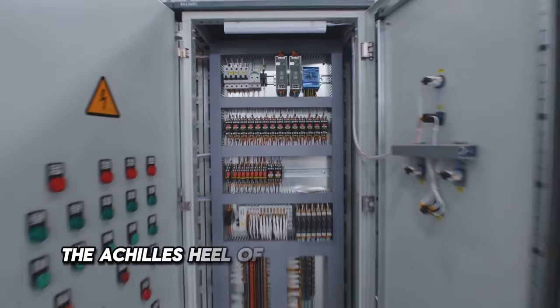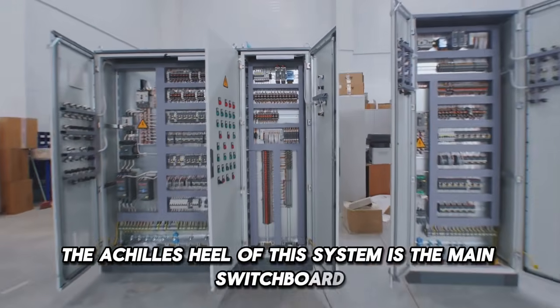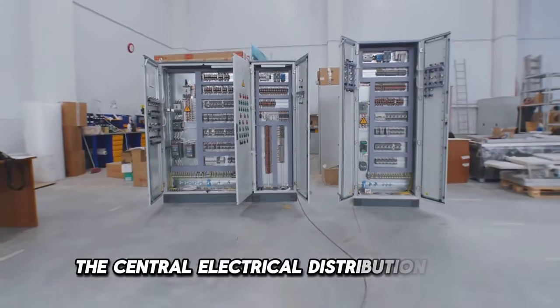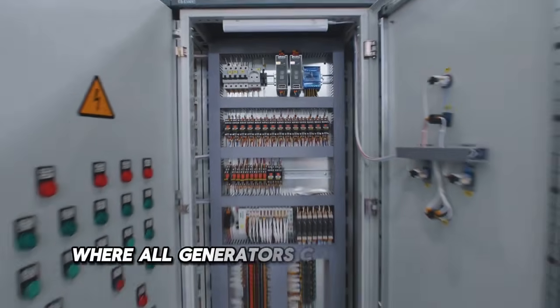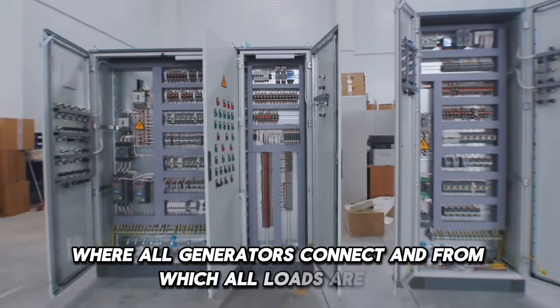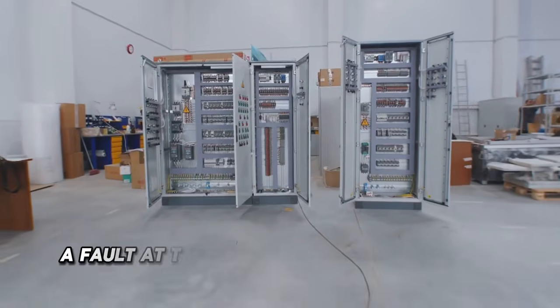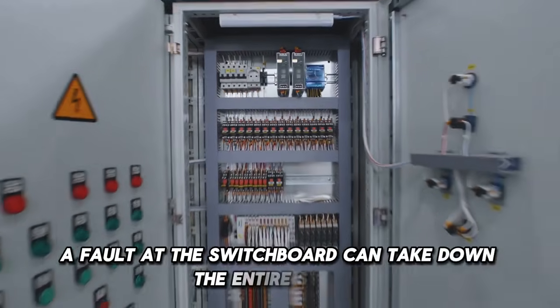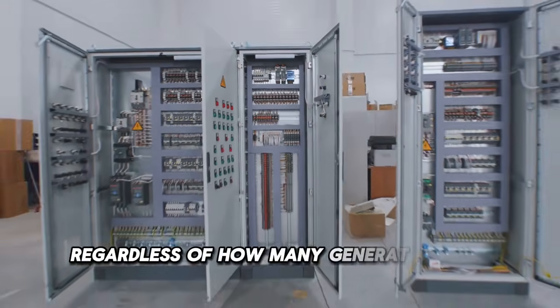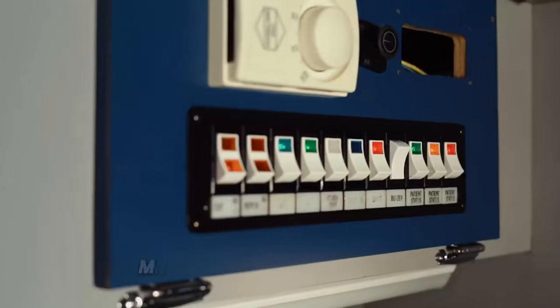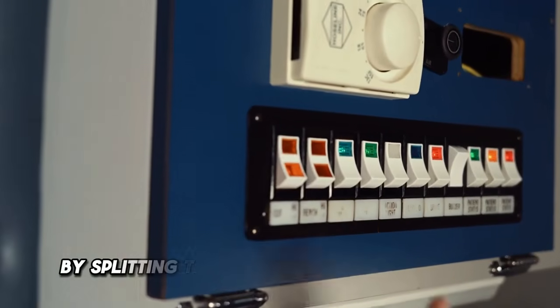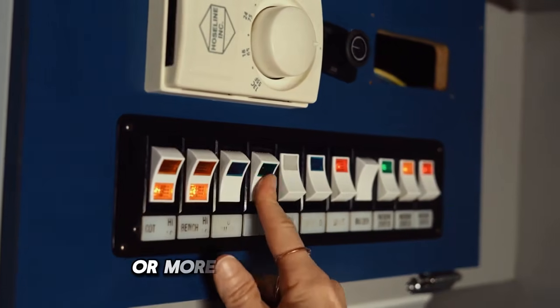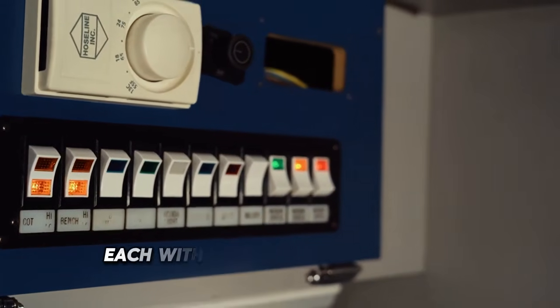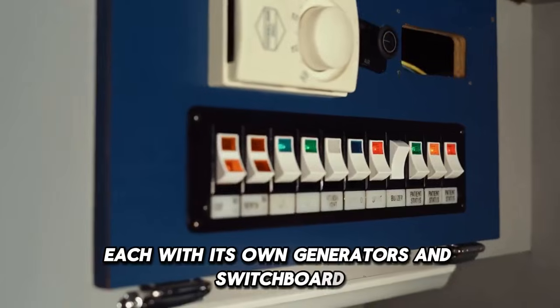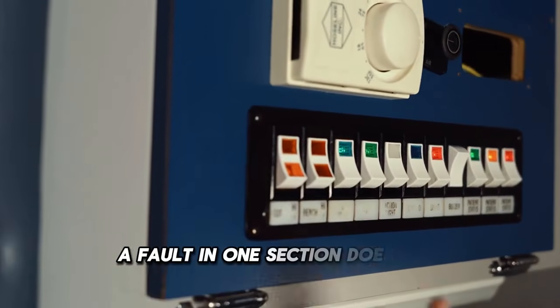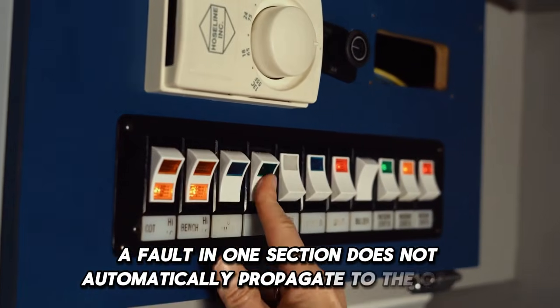The Achilles heel of this system is the main switchboard, the central electrical distribution point where all generators connect and from which all loads are fed. A fault at the switchboard can take down the entire system regardless of how many generators are running. Modern vessels address this by splitting the electrical system into 2 or more independent sections, each with its own generators and switchboard. A fault in one section does not automatically propagate to the other.